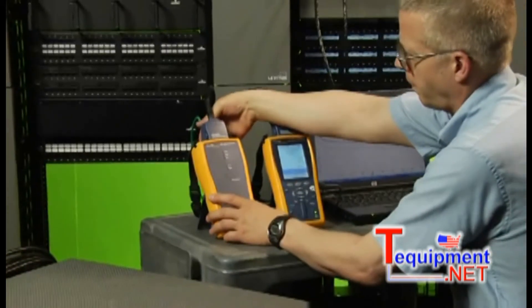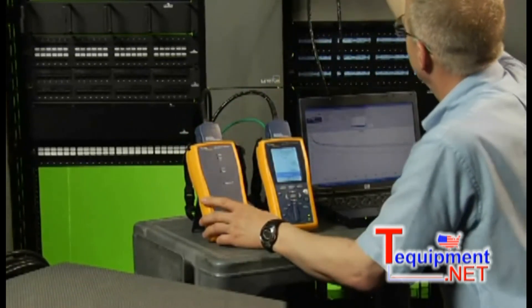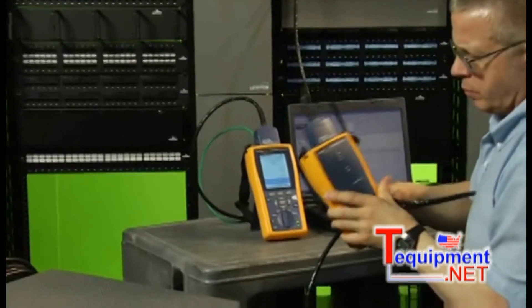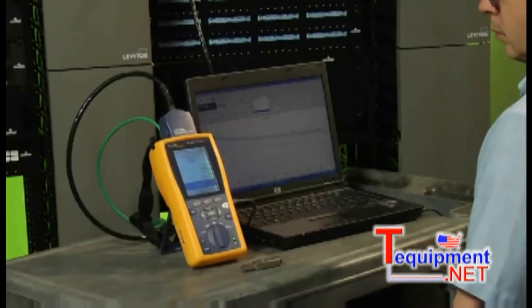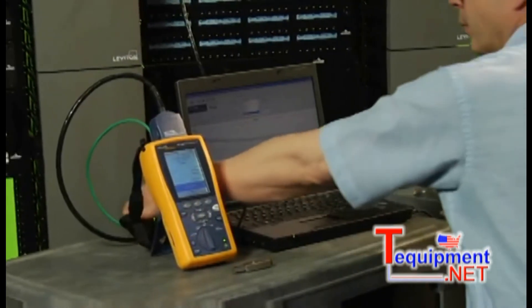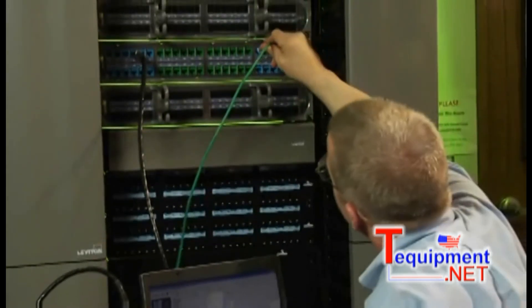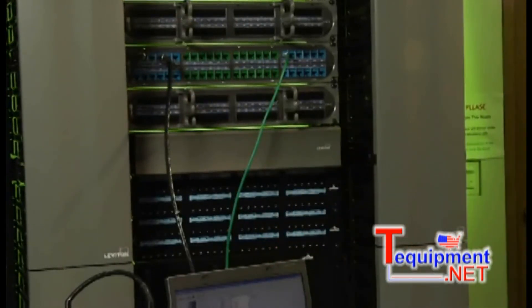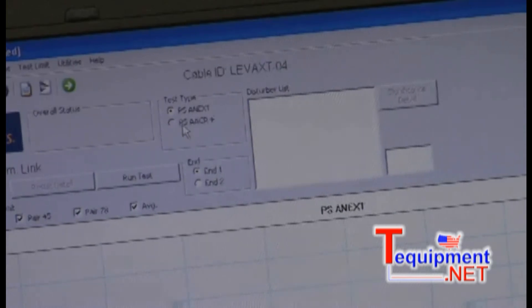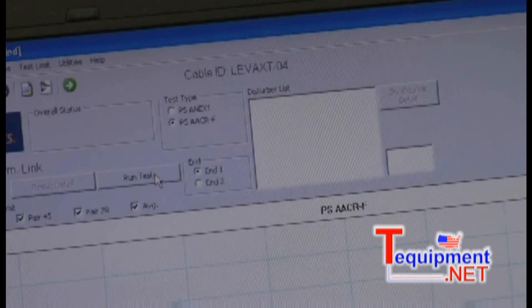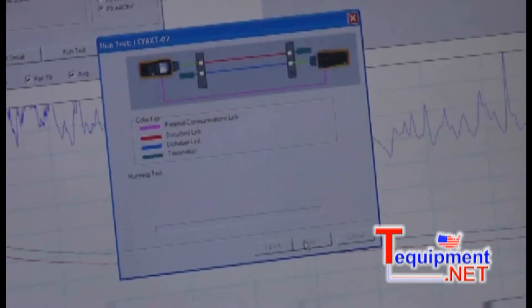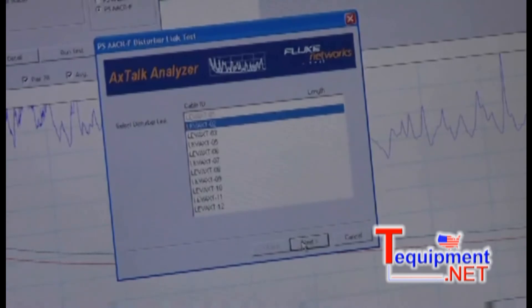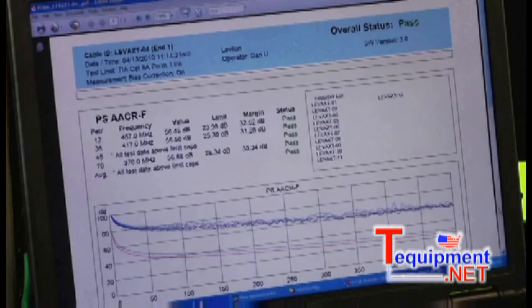Now we move on to the far-end testing. The setup is very similar to the near-end test, except we have to move the DTX remote unit to the other end of the link — the DTX main unit connection doesn't change. In order to synchronize the main and remote DTX units, we need to connect them up to a spare link — any link between the two panels but not the victim or the disturber under test — using a patch cord at either end. We terminate the disturber at the end where the main unit is plugged in. In our software, we change the selection to PS AACRF to indicate that we're testing from the far end and we run the test. Just like before, we get a pass or fail and move through the list of disturbers. After the last disturber has been added, we get a combined far-end test result.